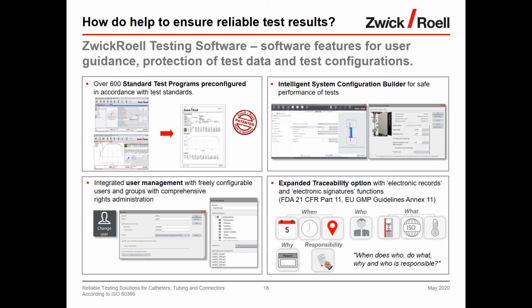First of all, the pre-configured standard test programs. That means there is no need for customers to go into the standards, checking the detailed requirements and entering them during the configuration of the test. We have already done that for the customers. The second one, the system configuration builder. First of all, this protects the sensors from being damaged. However, this is also very important when testing different products with different requirements regarding the configuration of the machine.